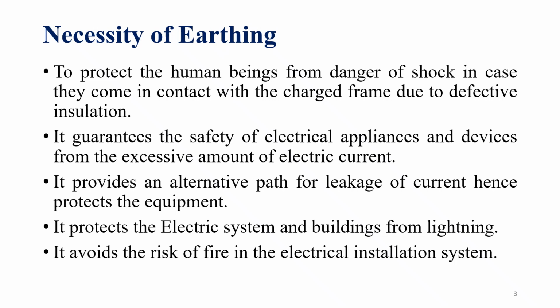As the leakage currents are passing through the earth, it gives safety to the electrical appliances also, and it provides an alternative path for leakage current. Whatever fault currents or leakage currents are developed in the system due to insulation failure or something else, they are passed through the earth through this earthing connection. It also protects the electrical system and buildings from lightning strokes, and it avoids the risk of fire due to short circuits or something else which leads to high currents.